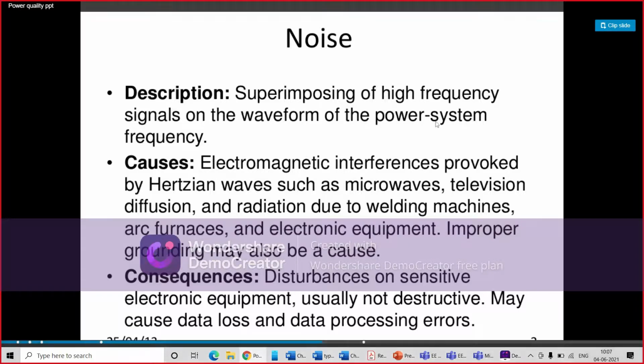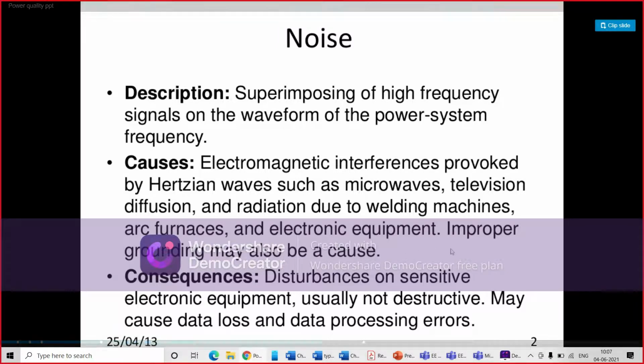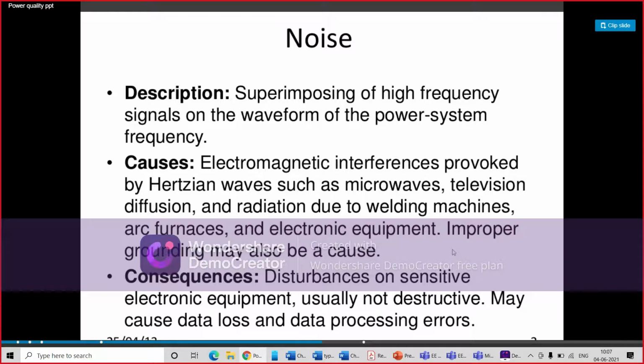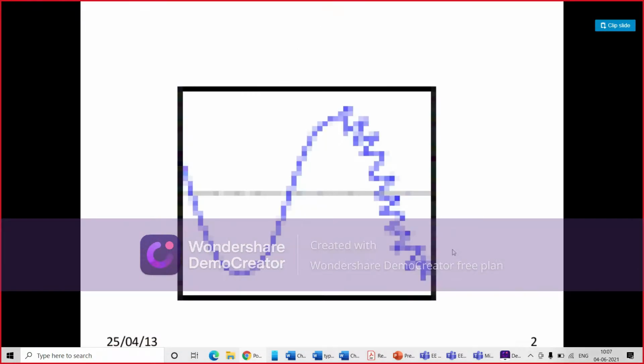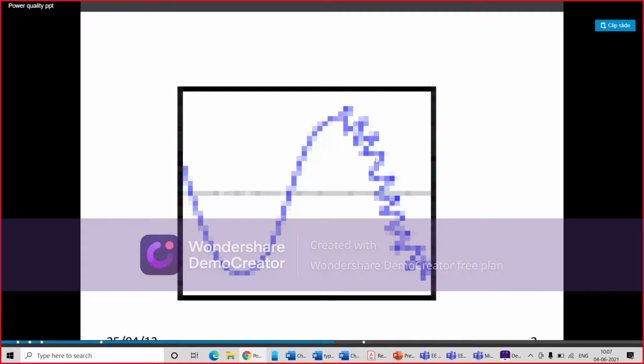So noise is the superimposing of a high frequency signal on the waveform of the power system frequency. Causes are electromagnetic interferences provoked by Hertzian waves such as microwaves, television diffusion, and radiation due to welding machines, arc furnaces and so on. What are the consequences? Disturbances on sensitive electronic equipment, usually not destructive, may cause data loss and data processing errors. In this particular scenario, the voltage looks like this.